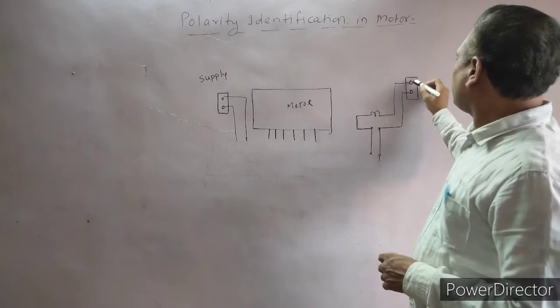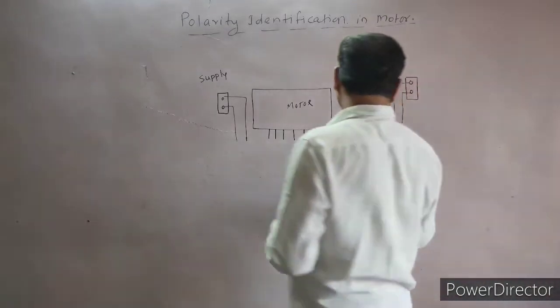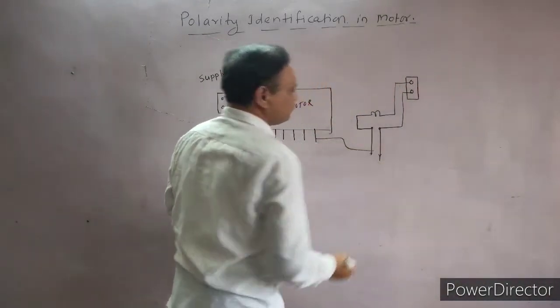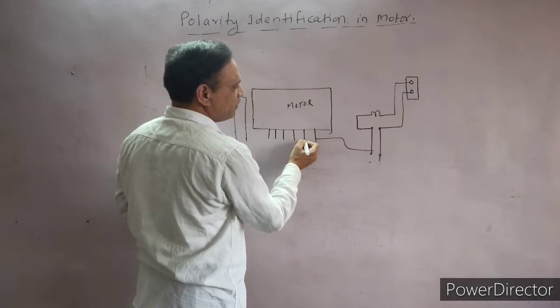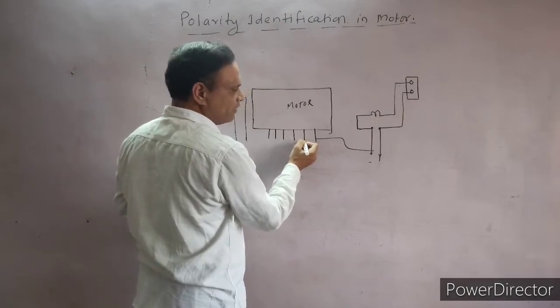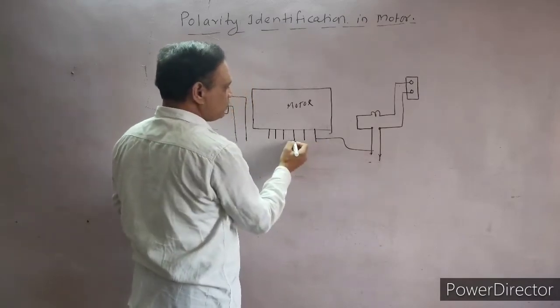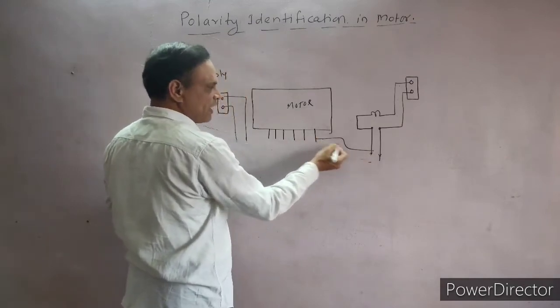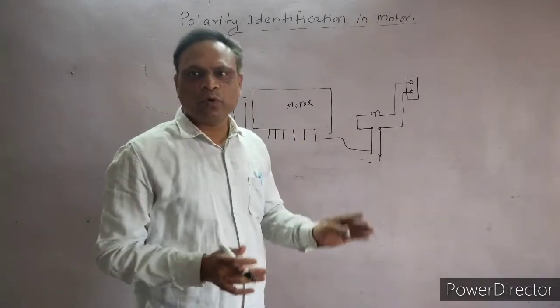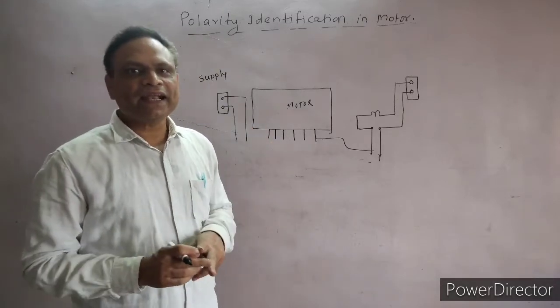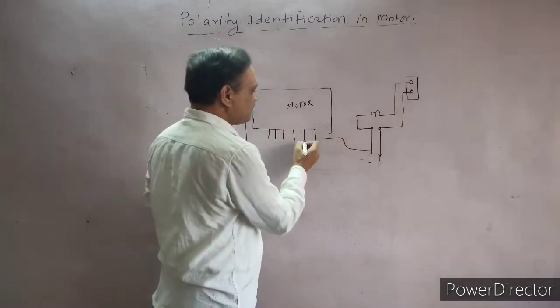First, make the switch on for the socket. These are the two probes of the series test lamp. We will connect one probe to a wire and keep it fixed, then move the other probe to each remaining wire. If there is connectivity and the lamp glows, then those two wires form a coil. If the lamp doesn't glow, there is no connection, so we move the mobile probe to the second, third, fourth, and fifth wire to find where the lamp glows.